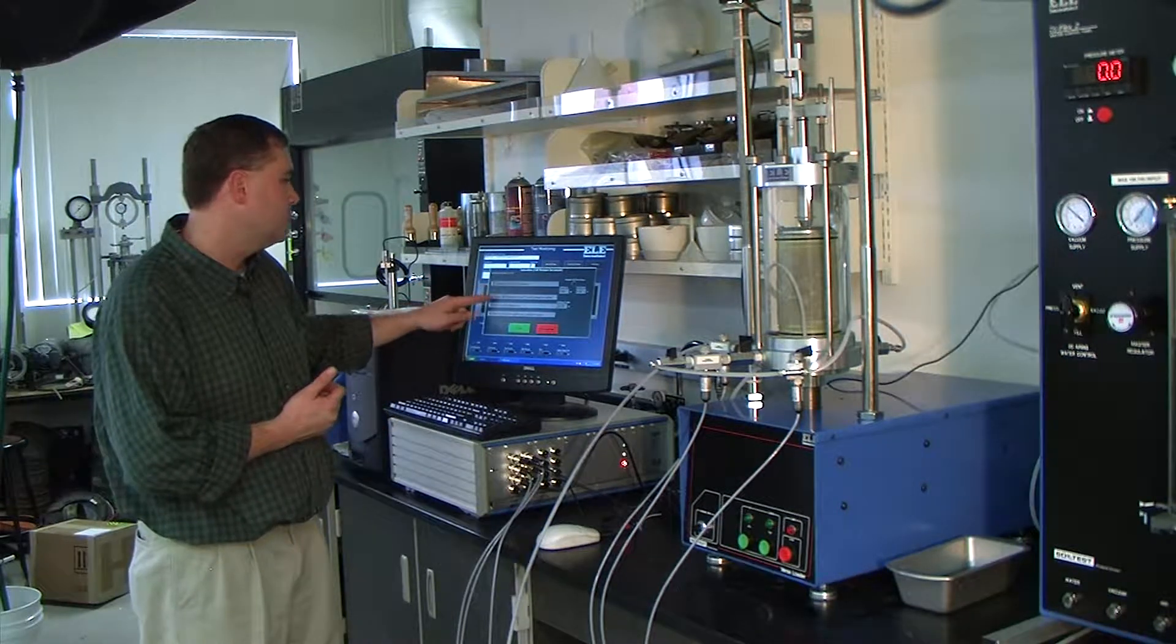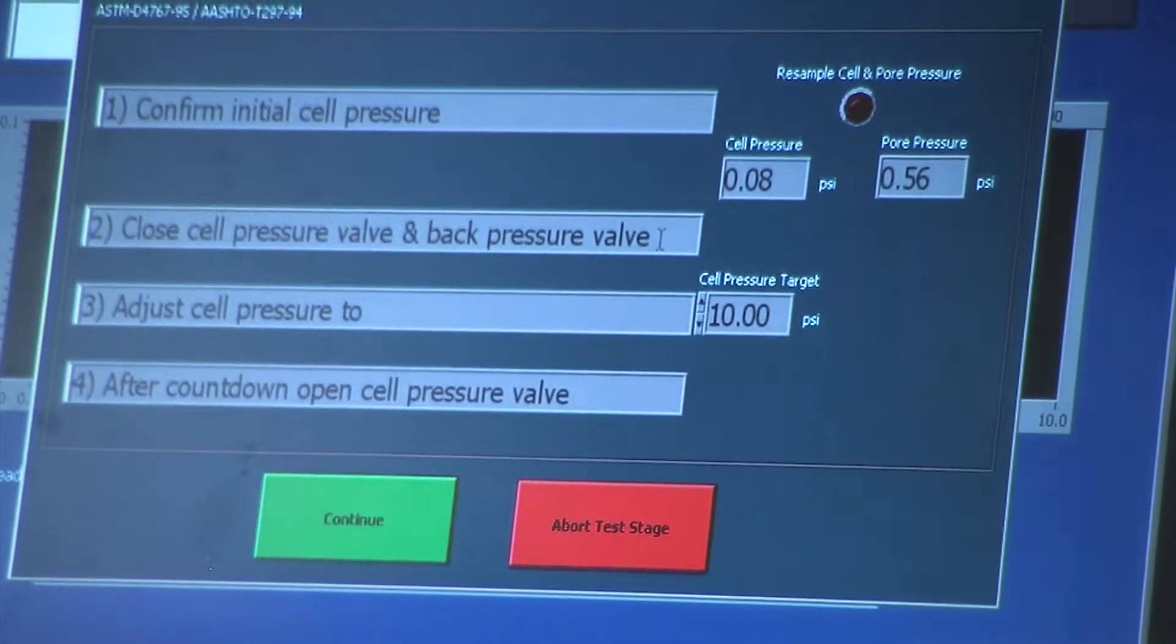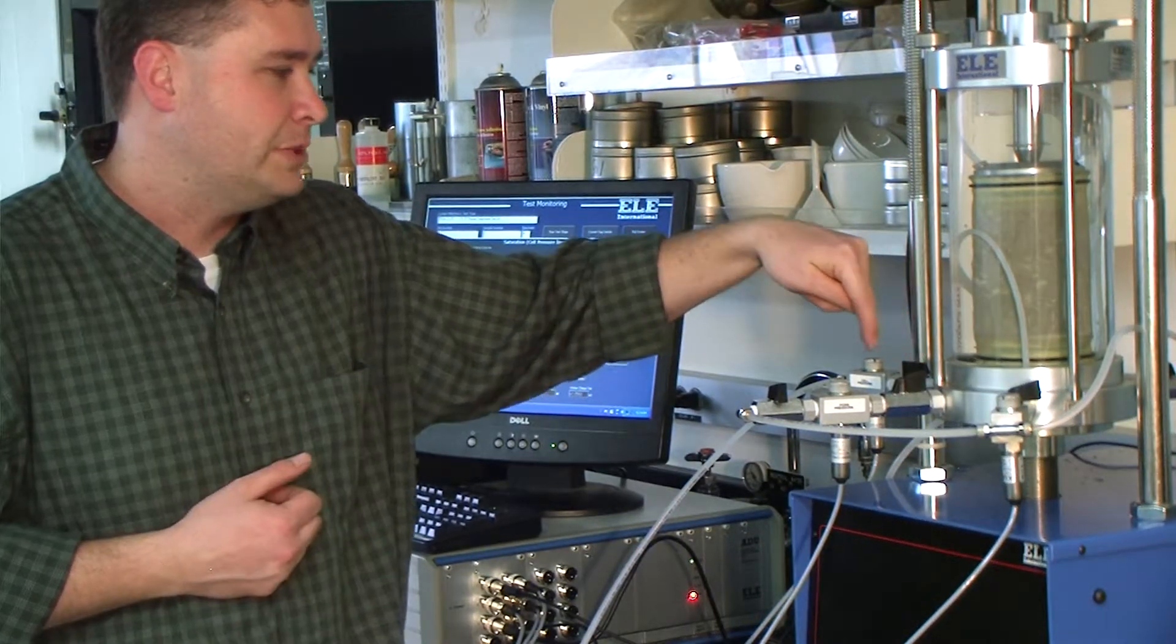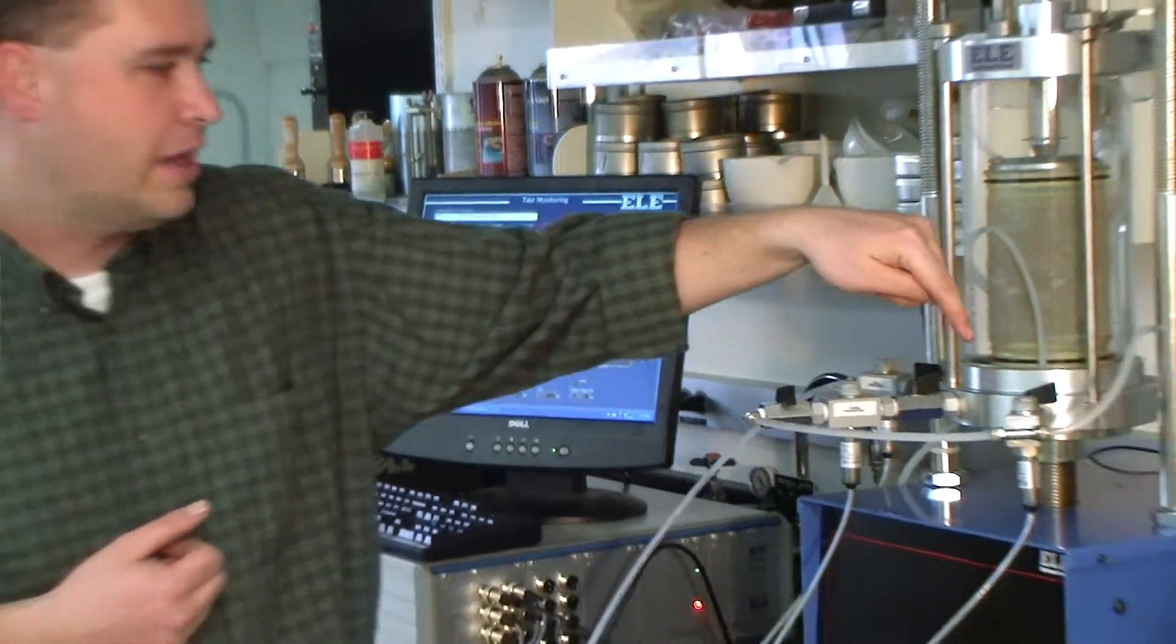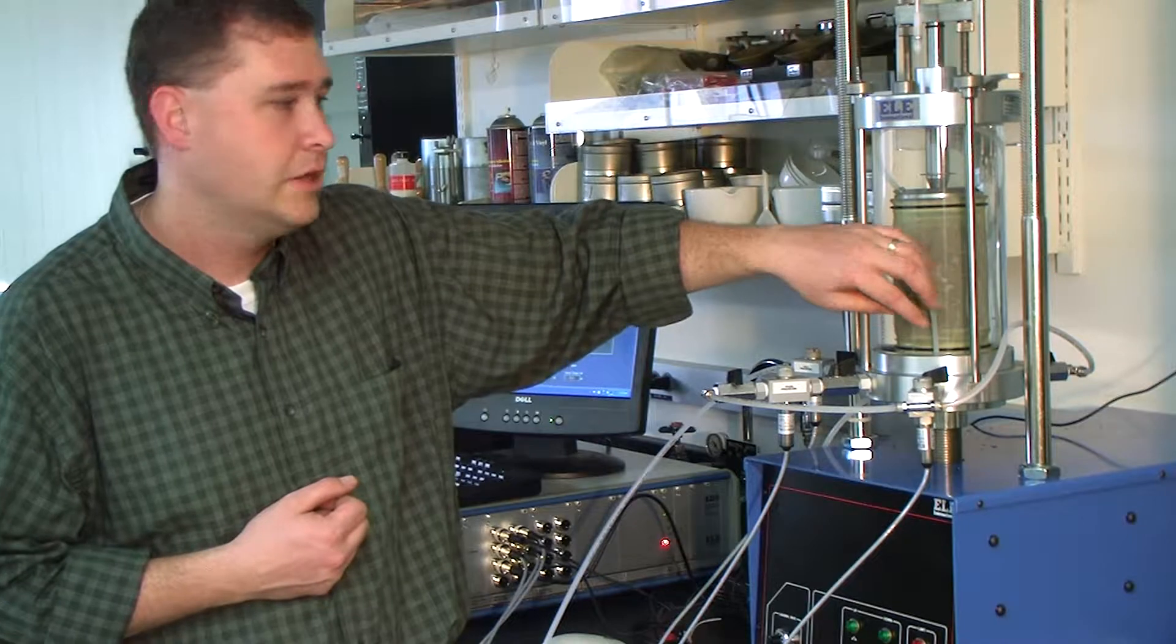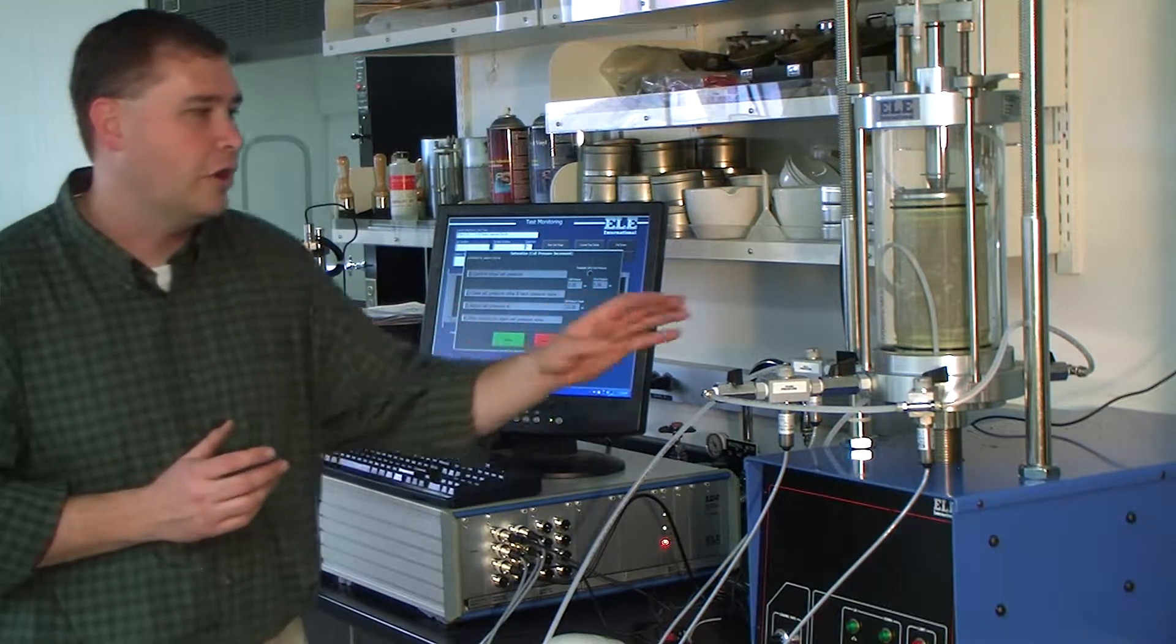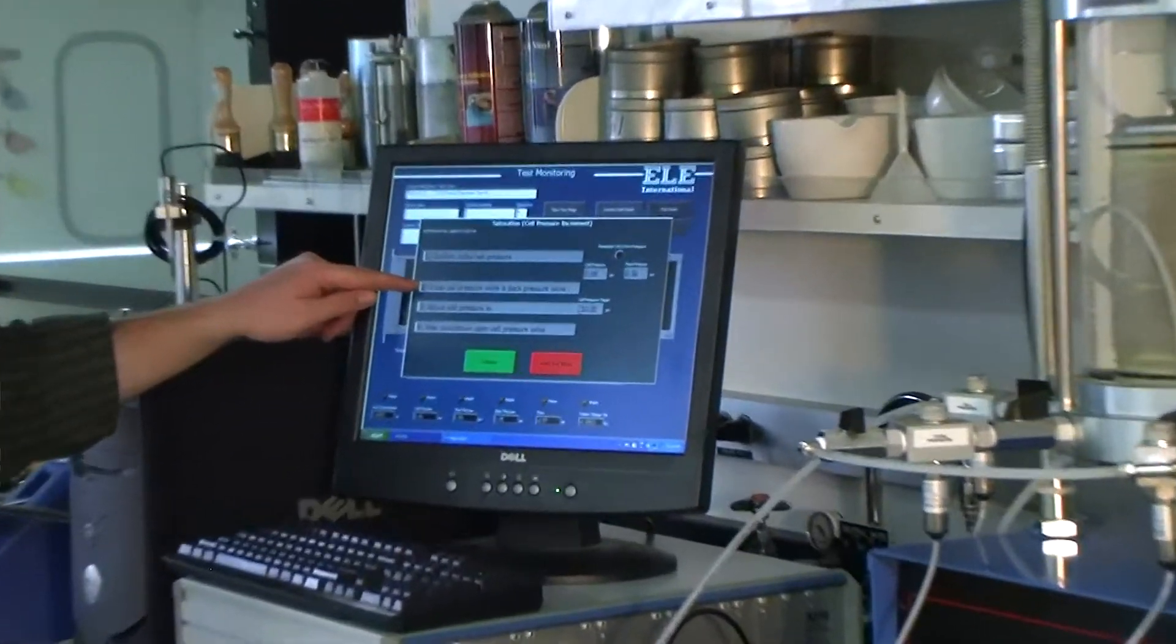The next step is step two, closed Cell Pressure Valve and Back Pressure Valve. When you first start, they're already closed, but I'll show you where they are on the cell. The Cell Pressure Valve is here, between the Cell Pressure Transducer and the cell itself. And the Back Pressure Valve is here, between the Back Pressure Transducer and the cell. Step two is already taken care of for us.